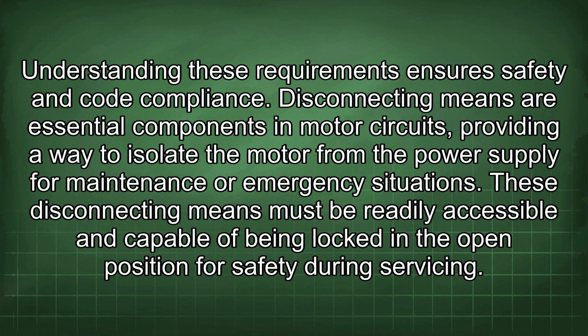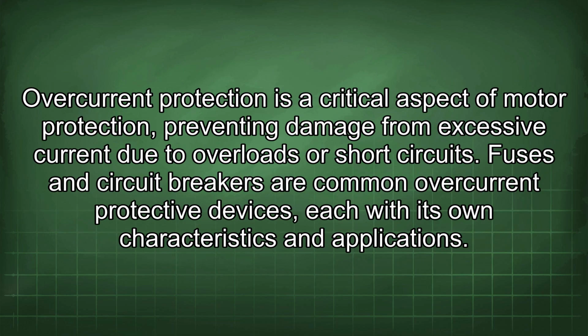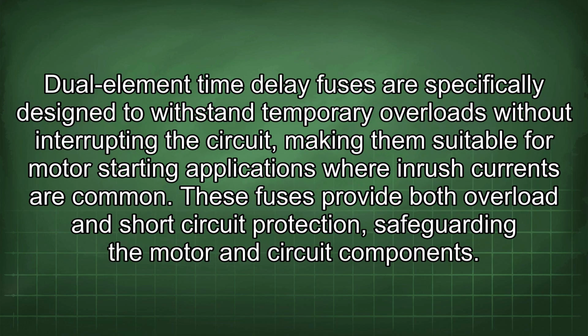for safety during servicing. Overcurrent protection is a critical aspect of motor protection, preventing damage from excessive current due to overloads or short circuits. Fuses and circuit breakers are common overcurrent protective devices, each with its own characteristics and applications. Dual-element time delay fuses are specifically designed to withstand temporary overloads without interrupting the circuit, making them suitable for motor start applications where inrush currents are common. These fuses provide both overload and short-circuit protection, safeguarding the motor and circuit components.